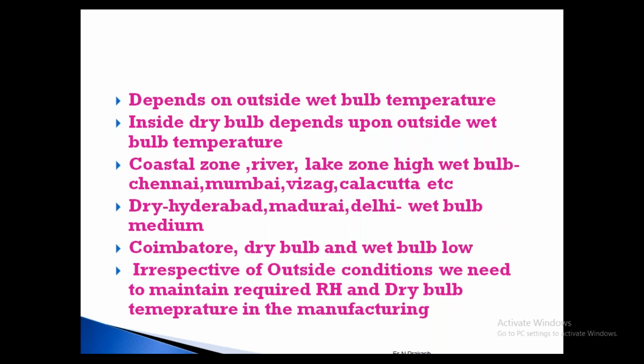Because as per psychrometric principles, only a humidification plant is working. If it is fully air conditioned, you can run at any dry bulb, any wet bulb condition. But in 99% of the textile mills, we work only on evaporative cooling. That is without refrigerant, only with water we spray and get the conditions. So it is all based on your outside wet bulb temperature, and also the coastal zone, river, lake add to your wet bulb. In a coastal region like Mumbai, Kolkata, Chennai, there will be more moisture, and you can see higher RH.